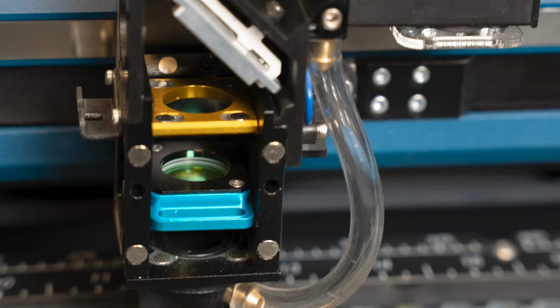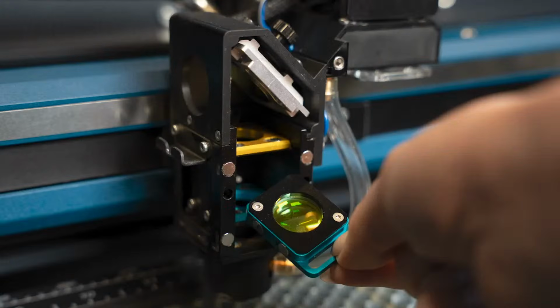They're color coded for which shelf inside the system they're supposed to go on. So there's, for example, a blue shelf in the middle, which corresponds to our 2-inch CO2 lens. And then above that, there's a yellow shelf, which goes with our 3-inch fiber lens. And then some of our accessory lenses go on the silver shelf at the bottom. But regardless, you cannot put them into the wrong location. They're pinned and keyed, and they can't be put in upside down either. And then it should be easy to change.